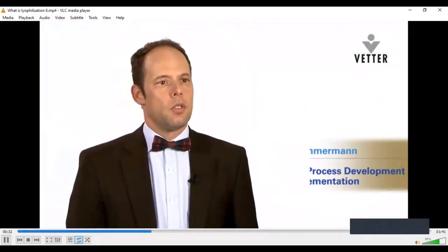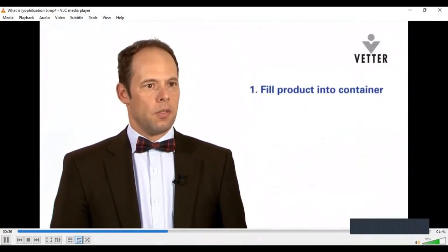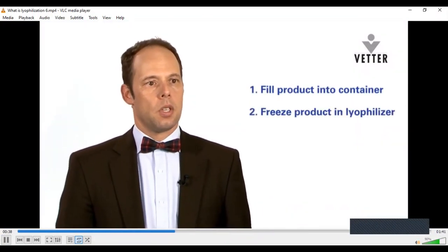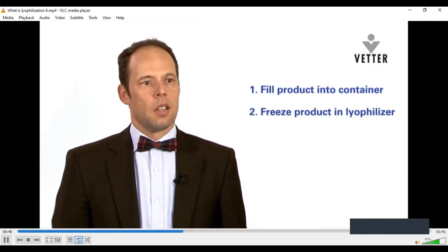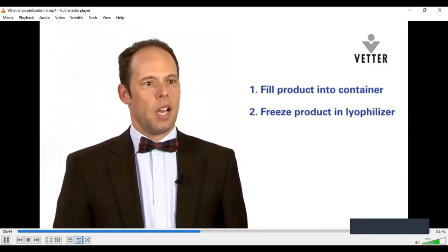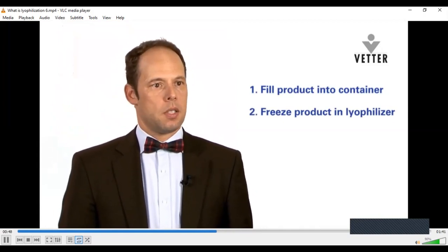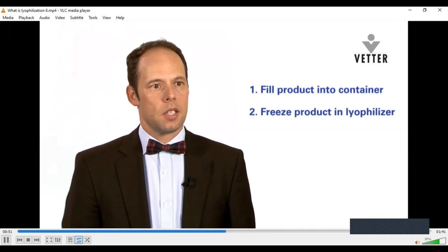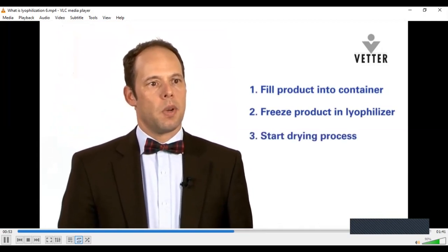For the lyophilization, the product is filled into the containers, into the syringes or the vials, and is then frozen in the lyophilizer. The freezing immobilizes all the constituents, all the things that we have in the solution to be freeze-dried. And after a certain time, at say -50 degrees Celsius, we start the drying process by applying a vacuum, which will then drive the sublimation.